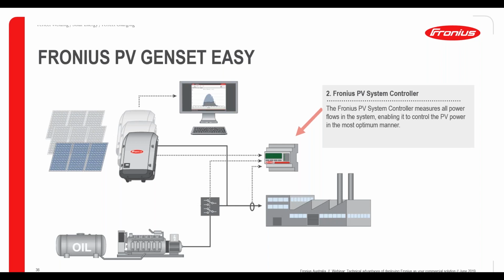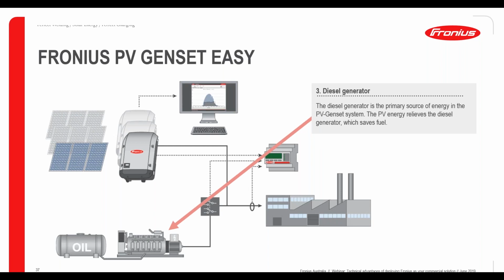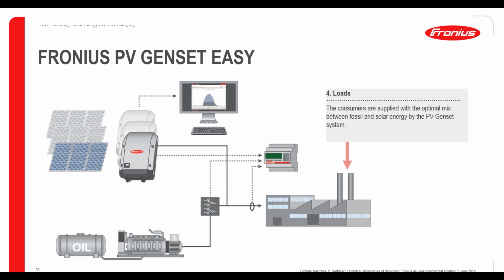Then you've also obviously got the genset itself, or the diesel generator. This is going to be the primary source of the power. Typically, we normally want to have the minimum loading on the generator at 30%, but I'll go through that in a minute. The actual loads that you're going to be matching the consumption with are typically maybe not an entire factory like in this scenario, but it could be, for example, irrigation pumps. It could be a lot of different scenarios whereby it's a closed scenario where you only have the diesel generator and the solar.